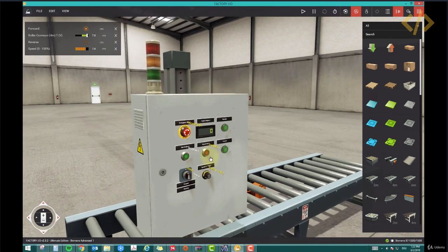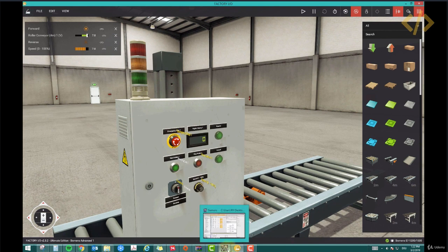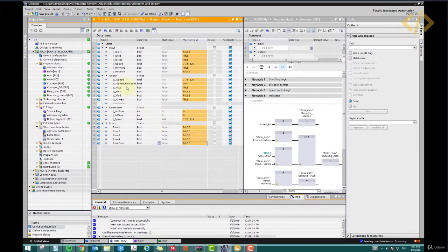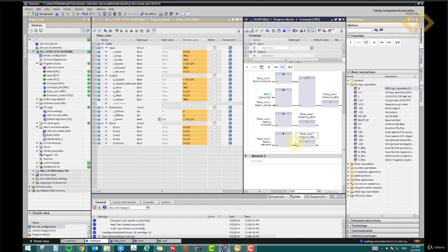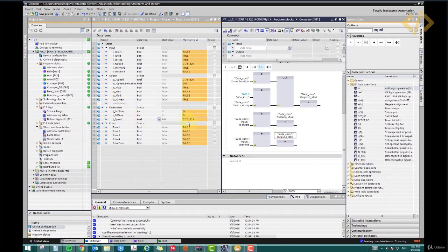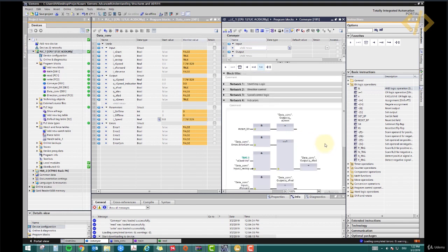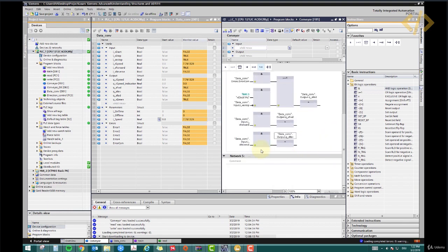Now in this integer, our actual value, if you notice in the parameter, is from 0 to 100, and for forward, where is that? Here, and 0 to 10 for forward, 0 to -10 for reverse. But we need from 0 to 100 and 0 to -100. So the gain is 10. So we can just make it in the indication, but I actually prefer such kind of calculations in the SCL, but nevertheless, we can make it here as well.